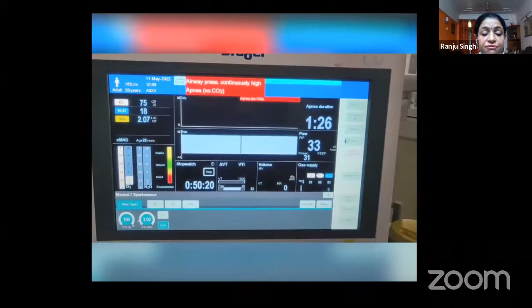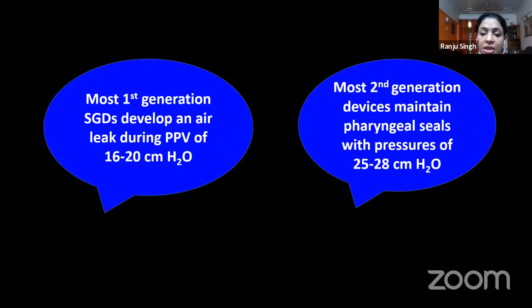Most first generation devices had low OLPs, only 16 to 20 centimeters of water. And most second generation devices maintain good oropharyngeal leak pressures with seals at pressures of about 25 to 28 centimeters of water. In some places, it's also mentioned as 26 to 31 centimeters of water. Individual second generation devices will have individual oropharyngeal leak pressures.